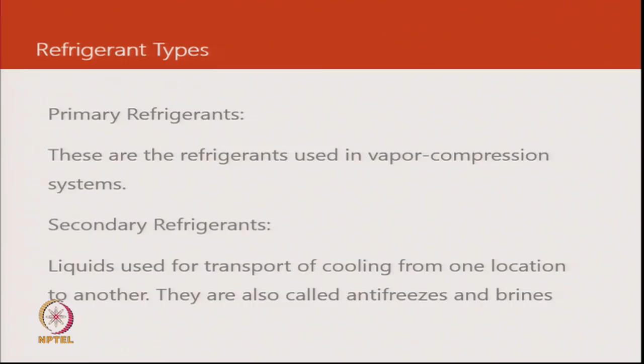So there are two categories into which we can split refrigerants. Primary refrigerants, which are a part of the vapor compression cycle. The secondary refrigerants are when we use the refrigerant as a means of heat transfer. So we want to take heat from one place, like in a chiller, where water is used as a secondary refrigerant. We cool it in the evaporator, and then the cold water goes into different terminal units where it cools the air that comes in contact with another heat exchanger. They are also called antifreeze and brines.